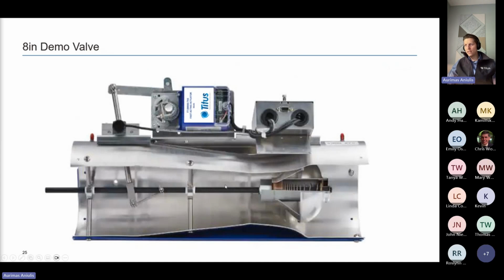But more importantly, the black thing is your cone shaft, and you can see the cone and the spring arrangement in there and how it sits in the airstream. If the air were to hit this, you would see this thing get compressed and this cone slide in towards this Venturi. Now, this is the narrowest part of the Venturi body, and these cones typically never go past that point. This is your ideal zero position cone.